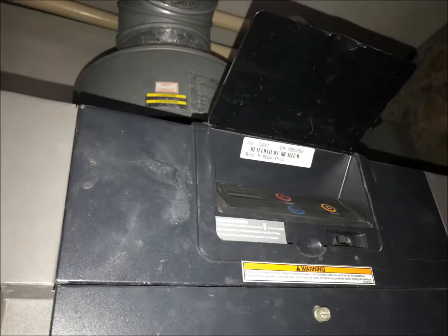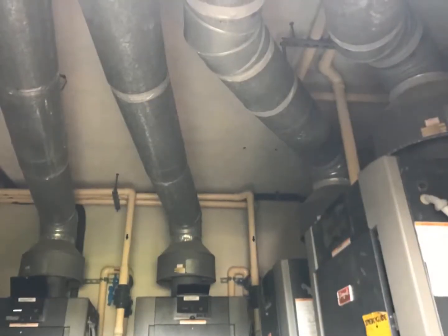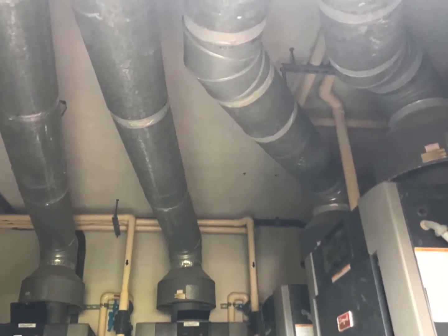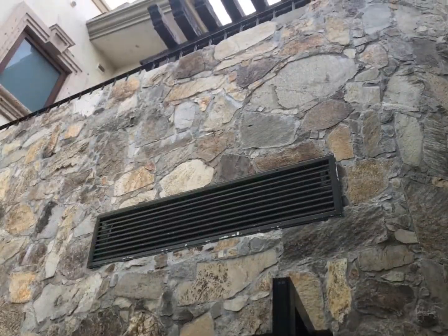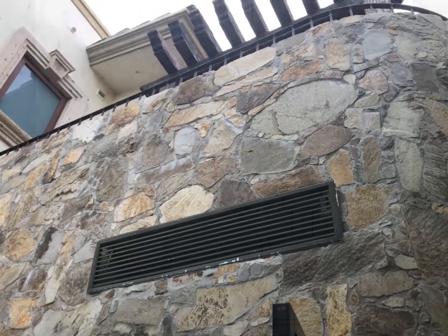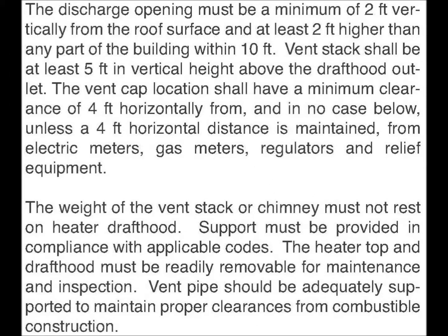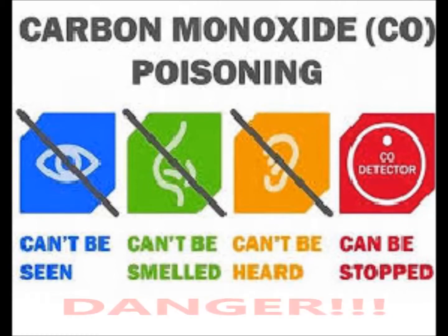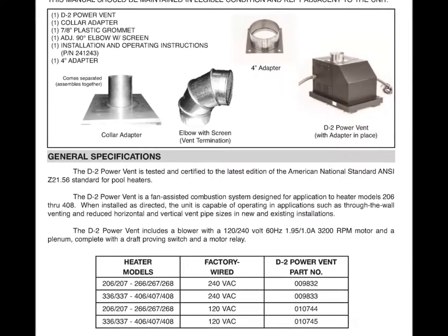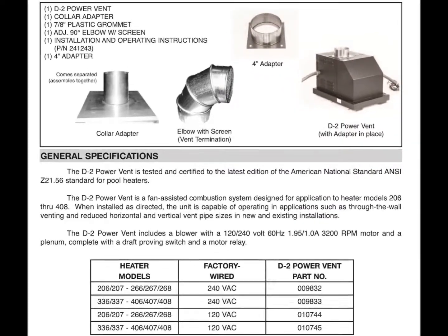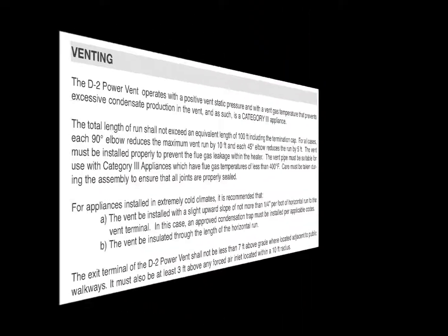There are four 400,000 BTU heaters located in the equipment room, and each has an intake and an exhaust airflow requirement. More importantly, the combined total of exhaust poses serious health risks if not vented properly. Here is the manufacturer's recommendation diagram for a single indoor heater, although for venting two or more heaters, it is noted to contact the factory. Carbon monoxide can't be seen, can't be smelled, can't be heard, but it can be stopped, and the potential for CO poisoning is a very serious issue.